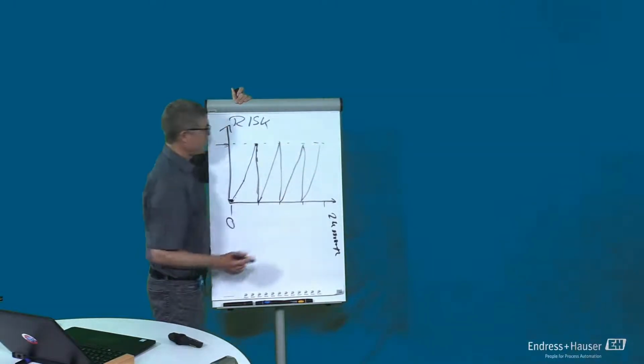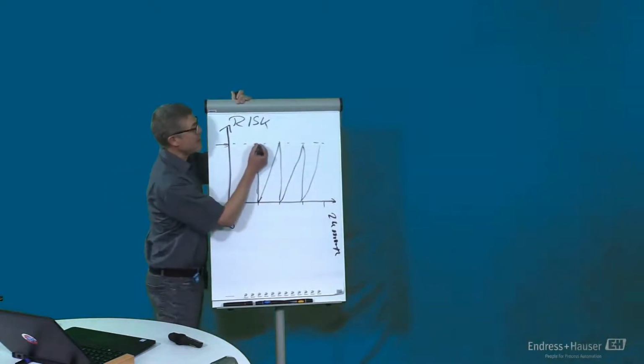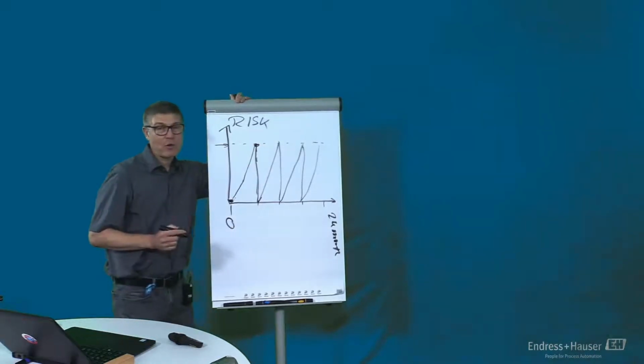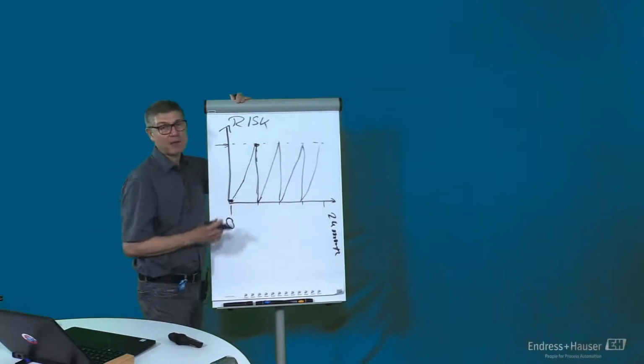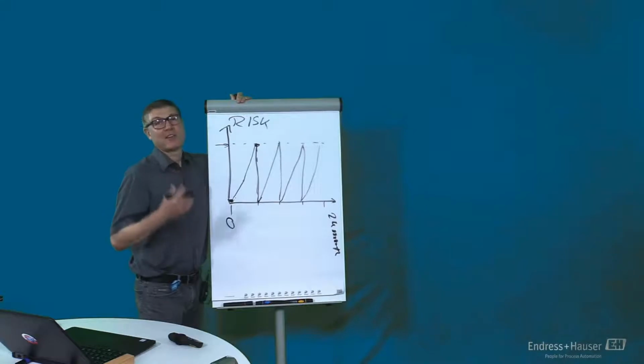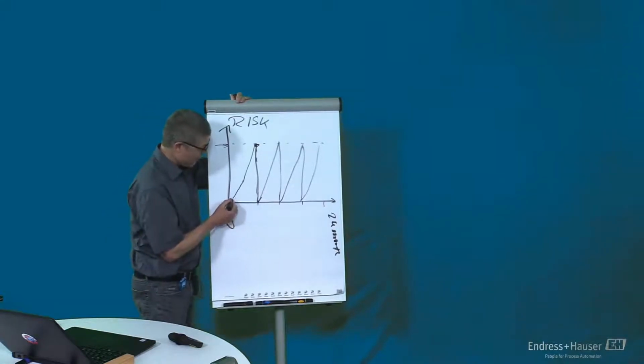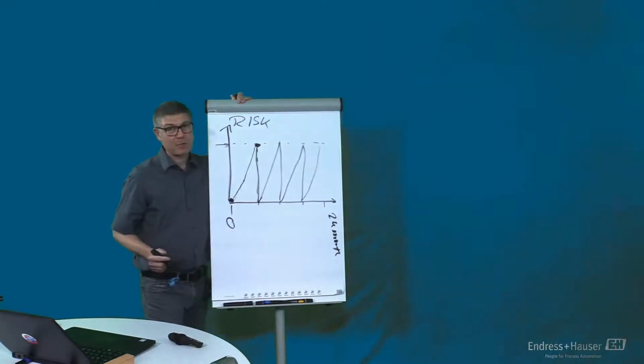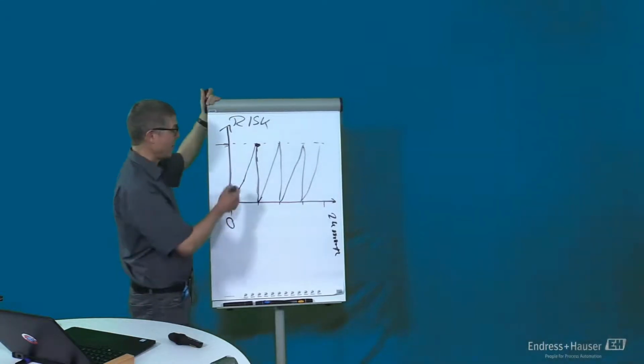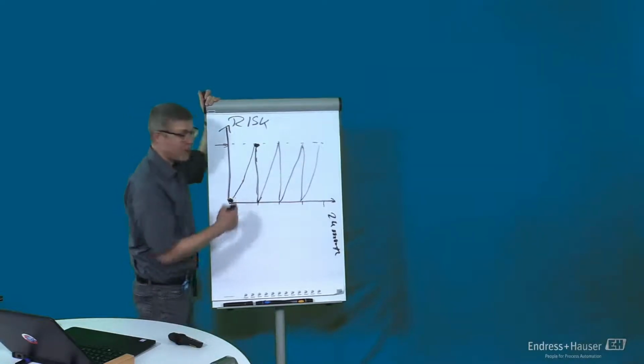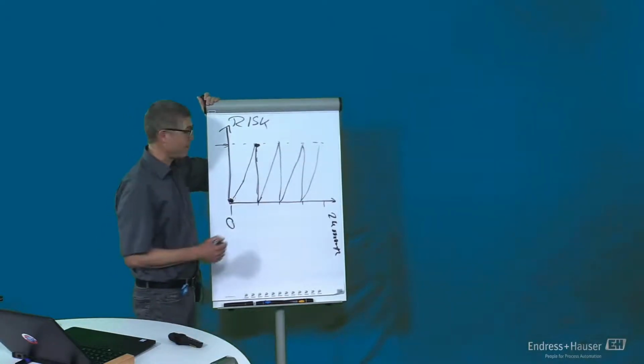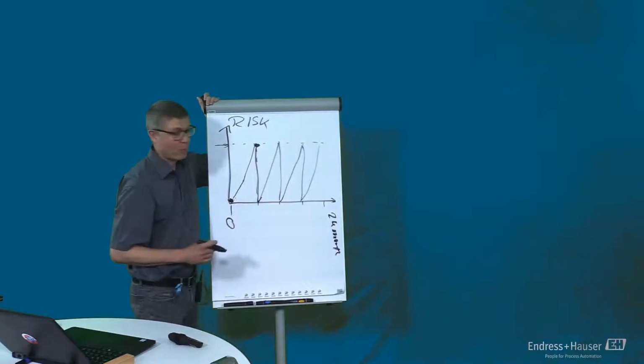So the problem here is, if you see that your sensor was not good 6 months later, since when was it not good? It was good here, it's not good at this point. Since when was it not good? You don't know. It could have been broken, it could have fallen out of spec directly after the calibration, or there was a drift, or whatever.